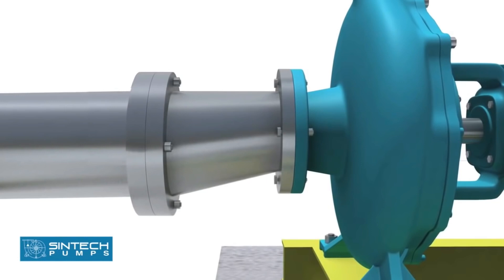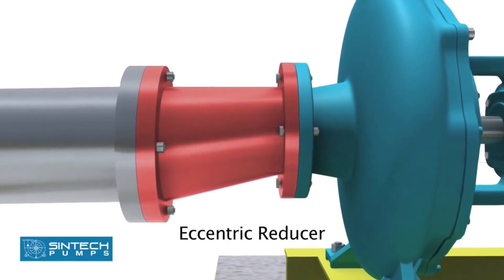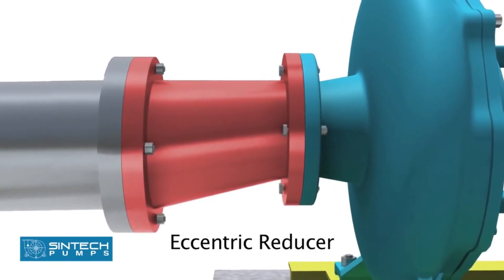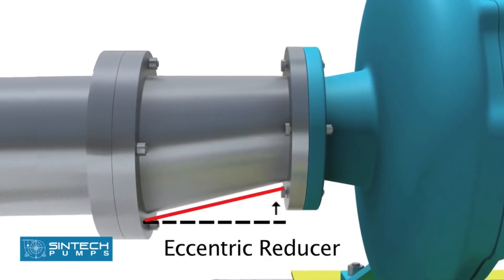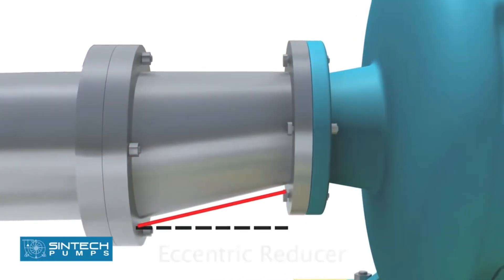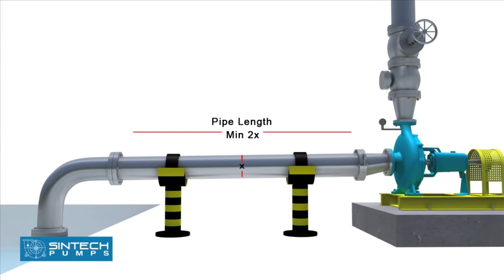The reducer joining the straight length of the pipe in the pump line should be an eccentric reducer with the inclined side of the reducer as the bottom side. The straight length of the pipe after the eccentric reducer should be two times of the pipe diameter.